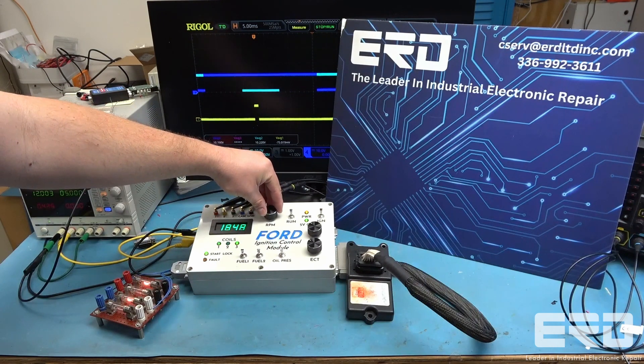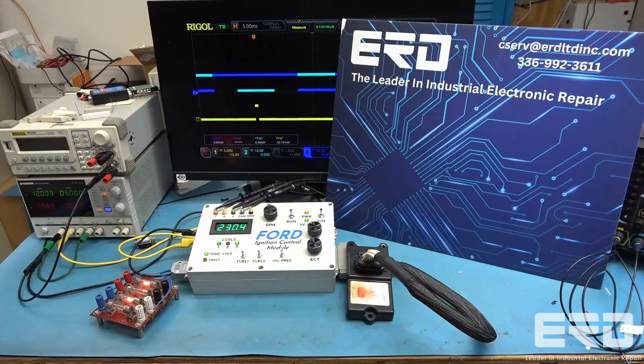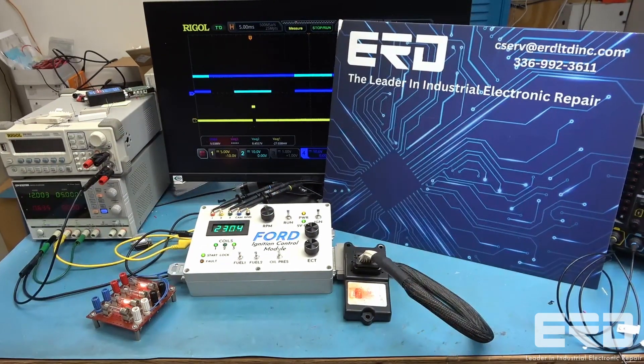ERD has developed a full and comprehensive test for these Ford ignition controllers used in heavy equipment, such as Genie boom lifts and scissor lifts.